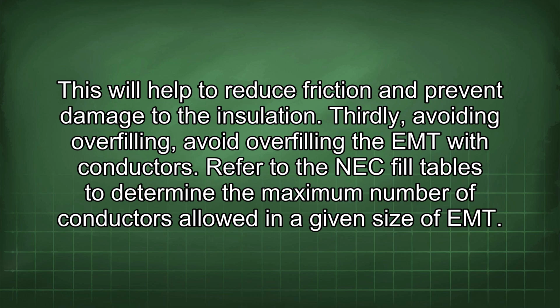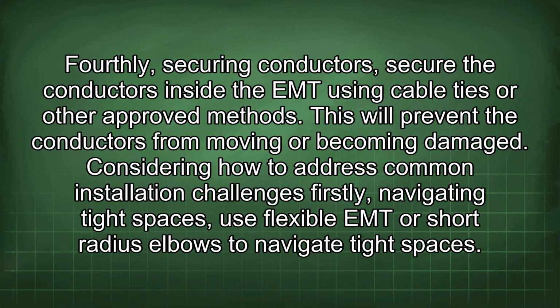Thirdly, avoiding overfilling. Avoid overfilling the EMT with conductors. Refer to the NEC fill tables to determine the maximum number of conductors allowed in a given size of EMT. Fourthly, securing conductors. Secure the conductors inside the EMT using cable ties or other approved methods. This will prevent the conductors from moving or becoming damaged.